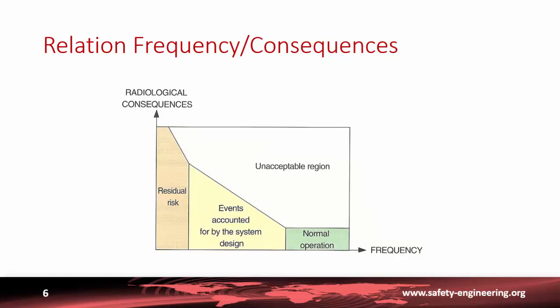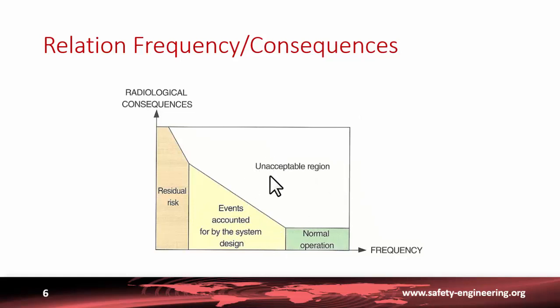An important design rule links the frequency of the accident or transient with the consequences: the higher the potential consequences, the lower the frequency should be. We can distinguish several regions. In normal operation, consequences should be very limited if not nil. At the other end of the spectrum, accidents with potentially high consequences should have a very low frequency — less than one in a million years. Between them, events are classified according to their frequency and consequence and should remain in the acceptable domain.